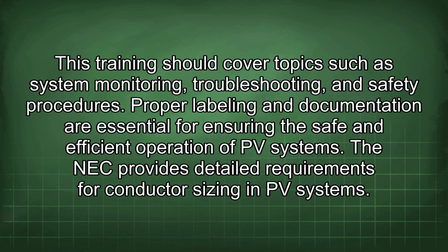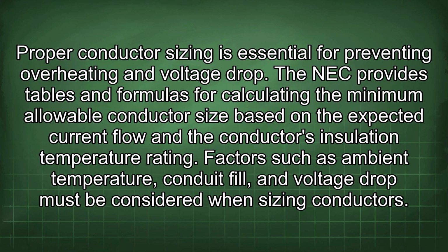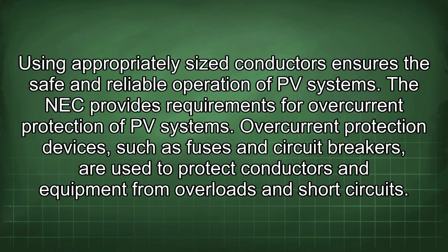The NEC provides detailed requirements for conductor sizing in PV systems. Proper conductor sizing is essential for preventing overheating and voltage drop. The NEC provides tables and formulas for calculating the minimum allowable conductor size based on the expected current flow and the conductor's insulation temperature rating. Factors such as ambient temperature, conduit fill, and voltage drop must be considered when sizing conductors. Using appropriately sized conductors ensures the safe and reliable operation of PV systems.